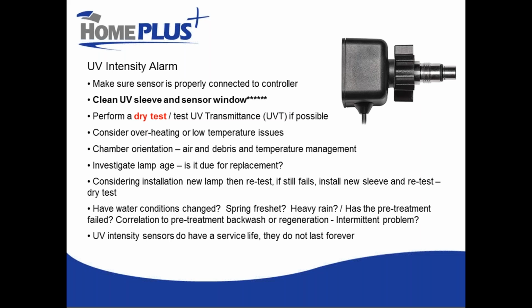So there's organic matter getting through that's absorbing the UV light, causing your dosage to drop, or there are sediment particles in the water that are interfering with the transmission of that UV light. If you don't have the UVT tester, you can still determine whether this is water related or equipment related by doing a dry test.